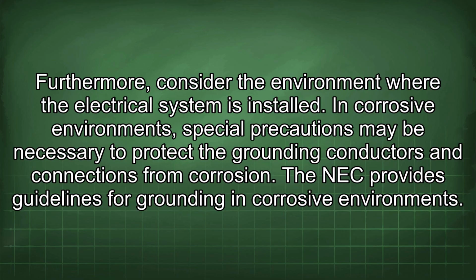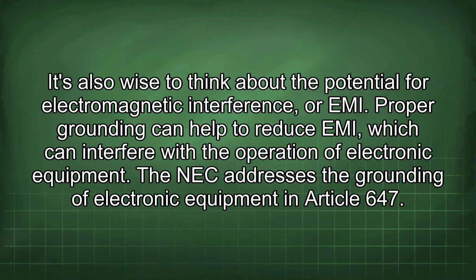Furthermore, consider the environment where the electrical system is installed. In corrosive environments, special precautions may be necessary to protect the grounding conductors and connections from corrosion. The NEC provides guidelines for grounding in corrosive environments. It's also wise to think about the potential for electromagnetic interference, or EMI. Proper grounding can help to reduce EMI, which can interfere with the operation of electronic equipment. The NEC addresses the grounding of electronic equipment in Article 647.